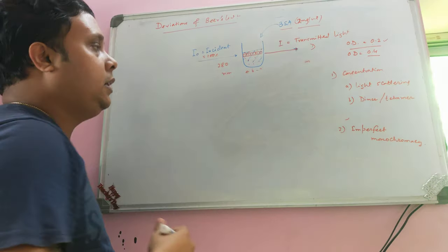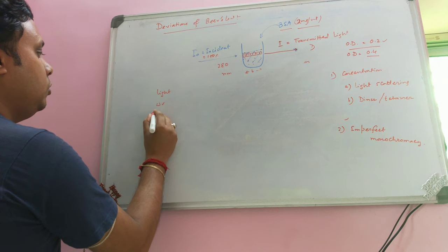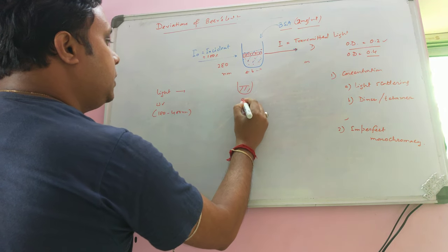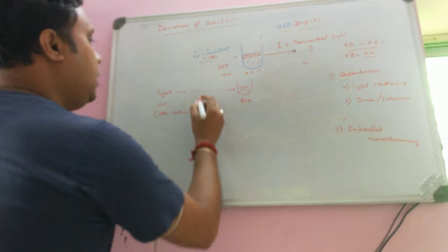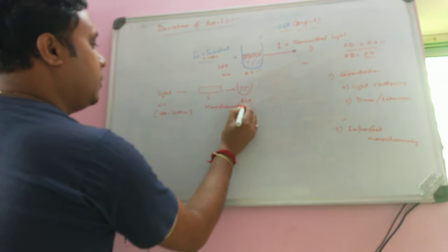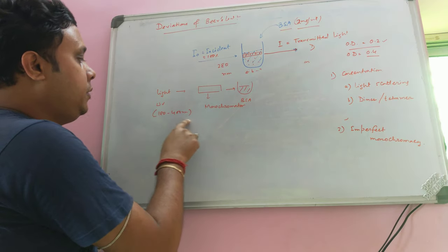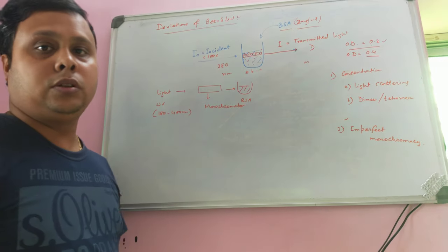For example, if we are measuring a protein like BSA, the incident light should be 280 nm, so we use a UV light source that can emit from 180 to 400 nm. We need to transfer only 280 nm to the sample, which is why we use an instrument called a monochromator. The function of the monochromator is to convert polychromatic light to monochromatic light — we command it to send only 280 nm to the BSA sample molecule.